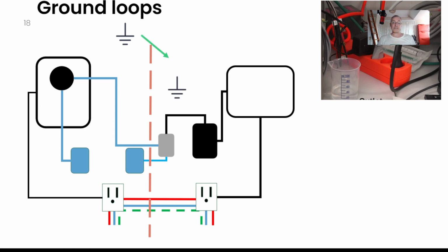And so you may have a signal where you're applying 650 millivolts and you have your glucose signal. But you've also got another signal that's actually due to this ground loop. And if anything, I'm thinking that the pump is at a slightly higher ground than the actual potentiostat. It doesn't make me right. It just would help me understand why you're getting apparently a negative current when in fact you're applying plus 650 millivolts to that glucose sensor.